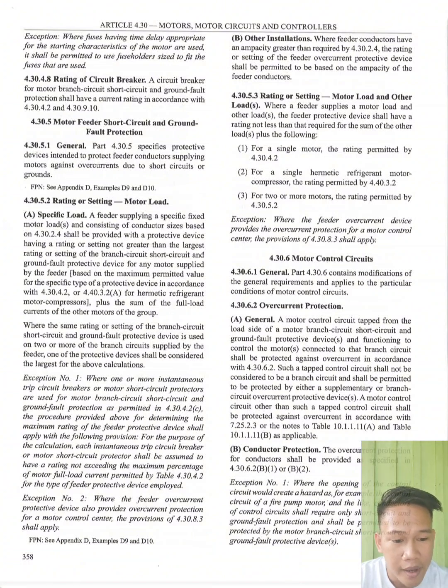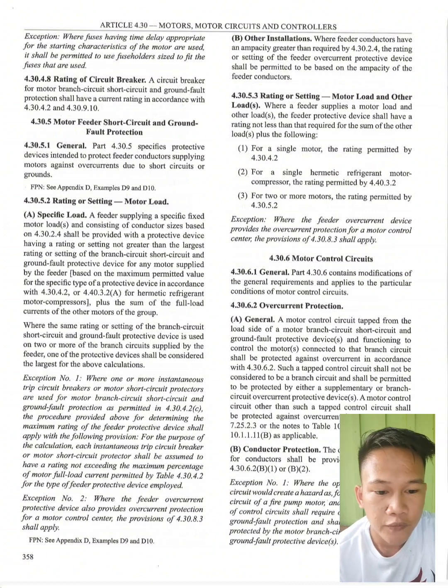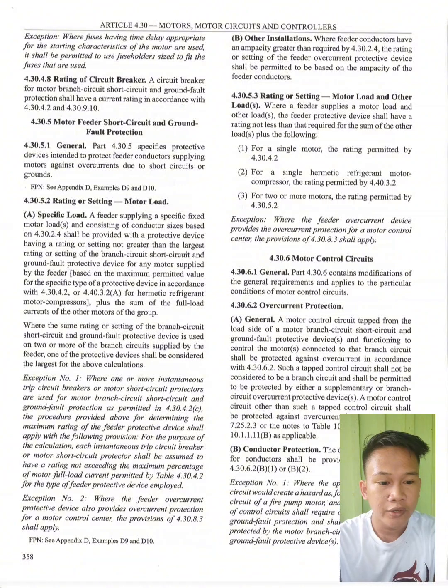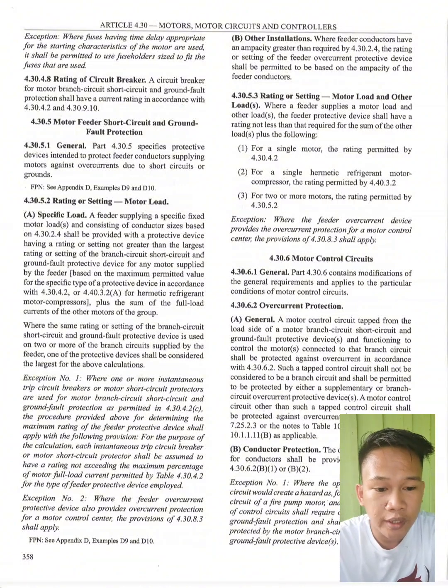A motor control circuit other than such a tap control circuit shall be protected against overcurrent in accordance with 7.25.2.3 or the notes to Table 10.1.1.11a and Table 10.1.1.11b as applicable. Next is conductor protection. The overcurrent protection for conductors shall be provided as specified in 4.30.6.2 B1 or B2. There are exceptions to this.